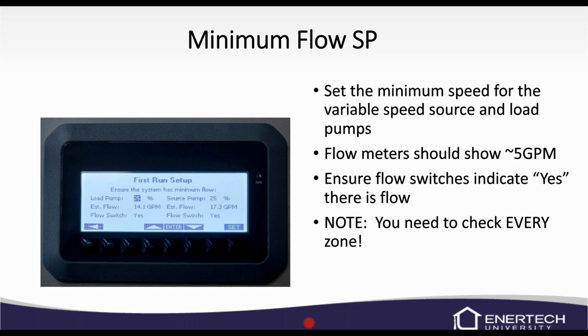The load, it's just really going to depend on your setup, but I've seen a lot of times somewhere between 25 and 40%. But just make sure we see 5 GPM, and that will be your minimum. So if that 25% is your 5 GPM, then that's where we need to set it. Always make sure your flow switch says yes, and you've got a minimum flow rate of 5 GPM on both the source and the load side.